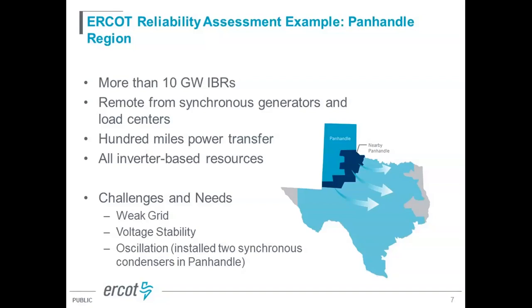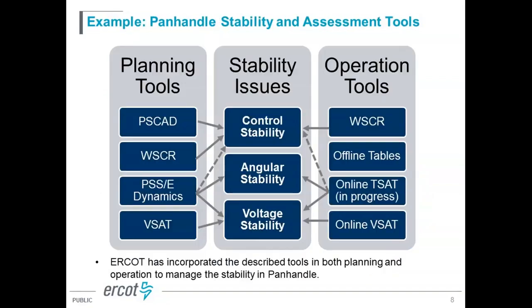The related challenges and needs, such as a weak grid, voltage stability, and oscillation: we put two synchronous condensers in the Panhandle to provide system strength and also to provide dynamic support. So we do have two synchronous machines, in terms of synchronous condensers, in the Panhandle region. The associated synchronous machine related stability, like angular stability and inter-area mode, also needs to be addressed. So how do we address this from the planning and operations perspective? This shows, at a very high level, the tools we use and how we identify and address the stability issues for the Panhandle region.